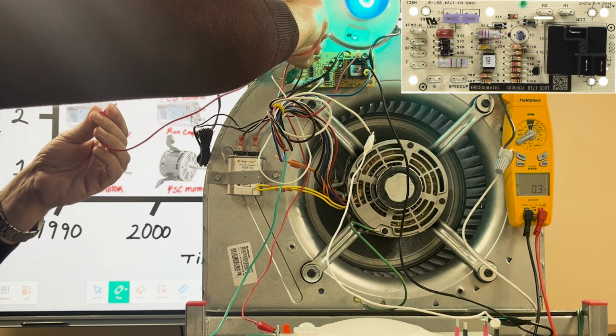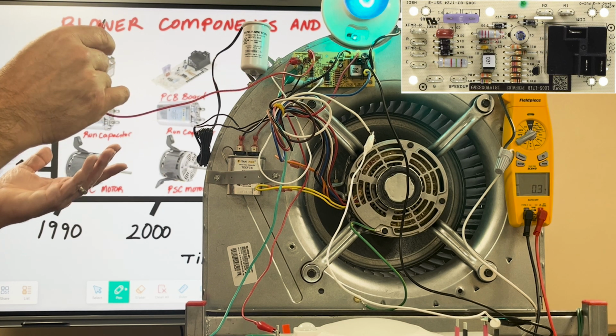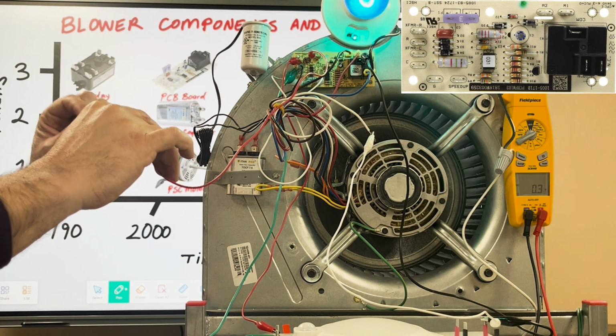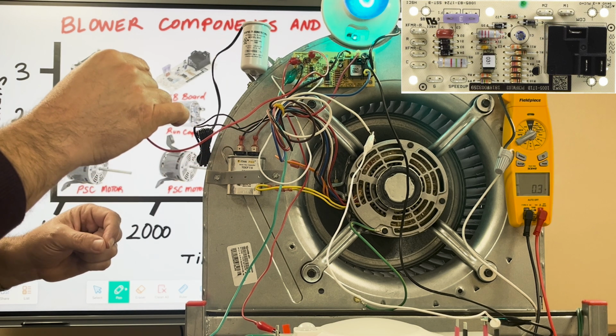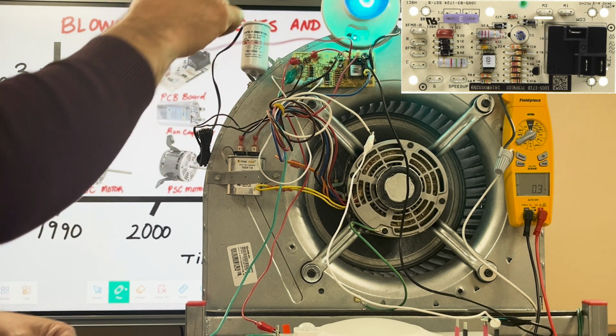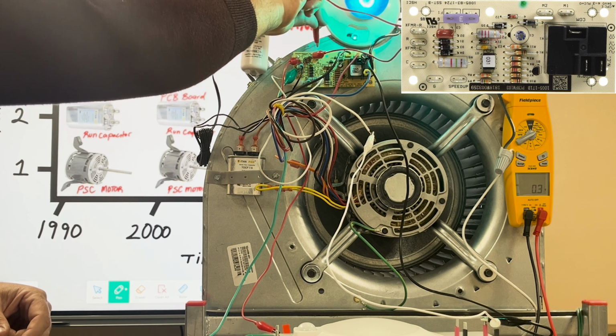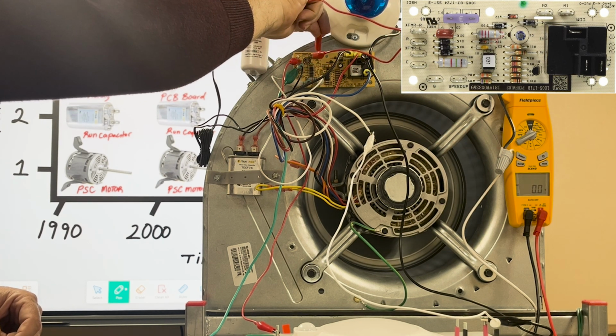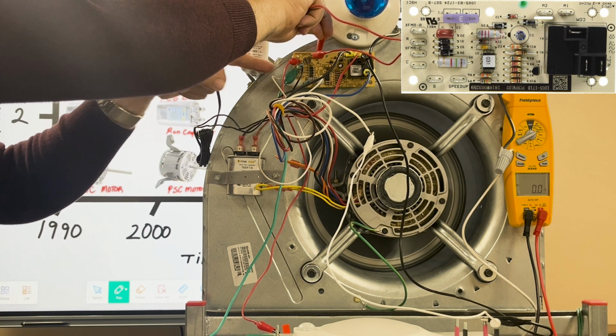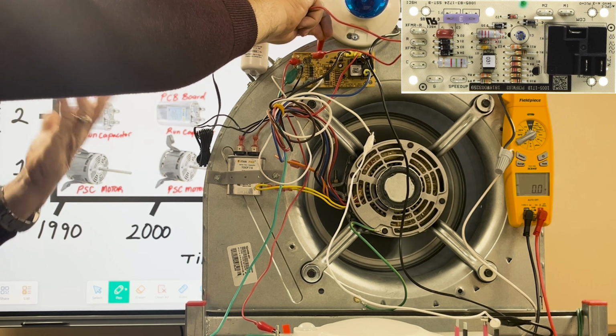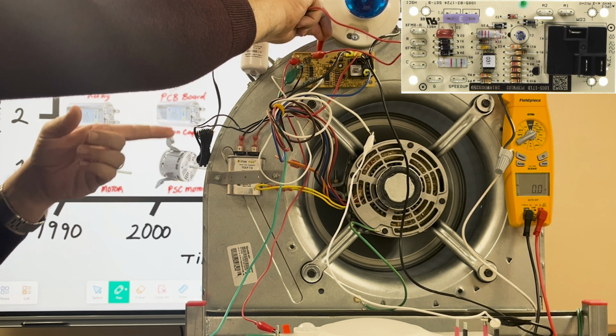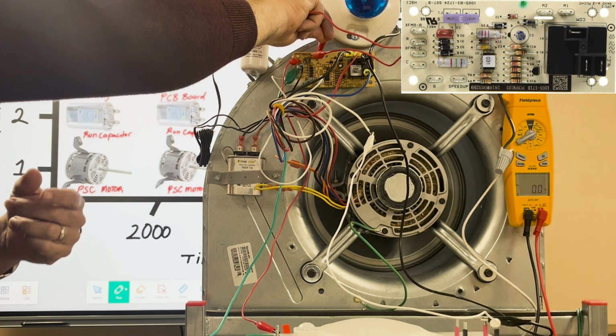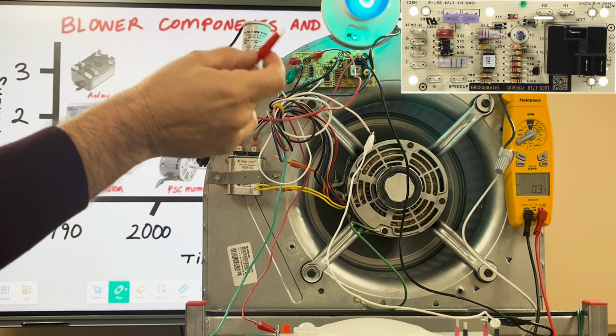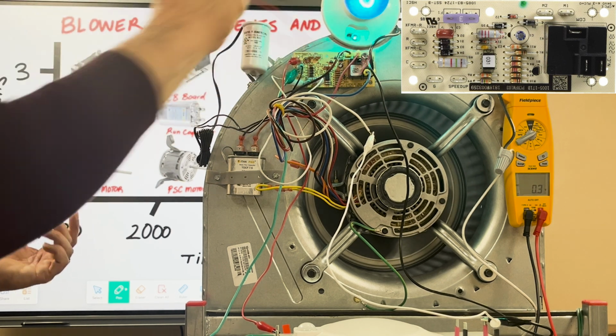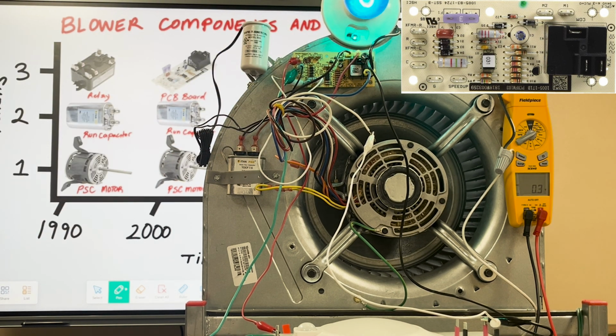So I'm going to go ahead and close this. I know I don't have any shorts here, so it's safe for me to do this, but never bypass your fuse. Your fuse is blown for a reason. I just want to show you that if I were to short these out, then I have 24 volts now on my R coming out through my float switch, out of my float switch, theoretically, into my thermostat, out of my thermostat, over to G, and because G is shorted out, there's no time delay. Now, if I lose 24 volts, everything shuts off. So this would represent an open fuse. This had a 3 amp fuse in it.